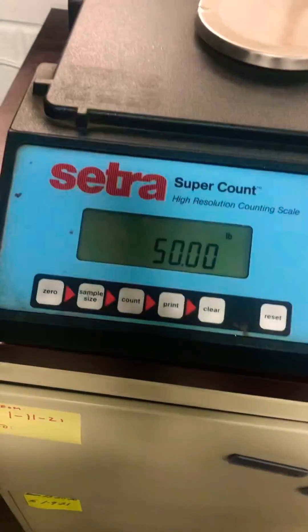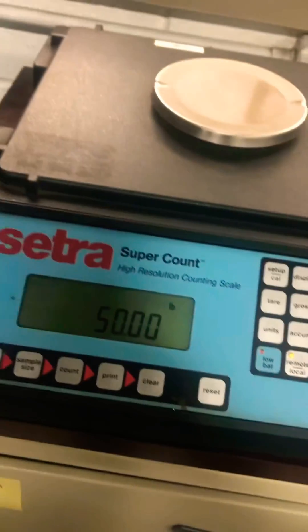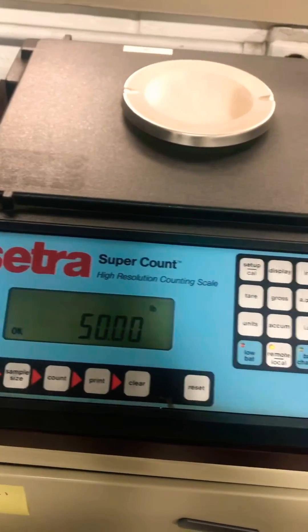50 pounds. Take one off — 25. Put it back on — 50 pounds. And that's how you adjust the calibration of a remote base that's hooked up to a Setra Super Count.